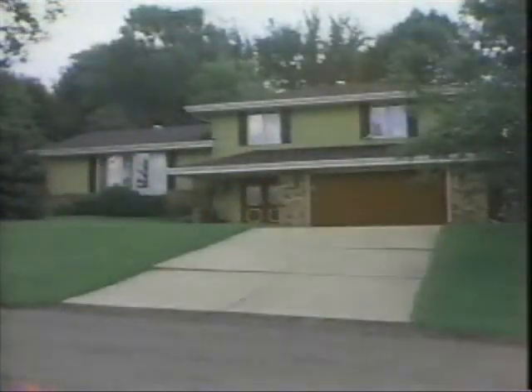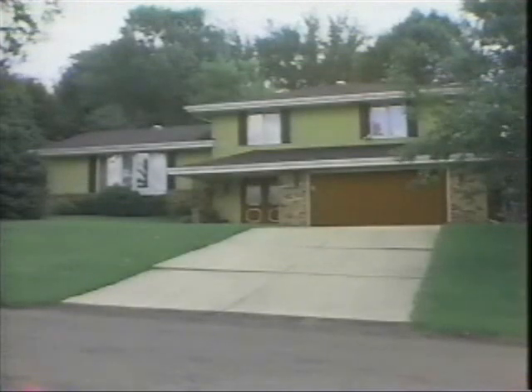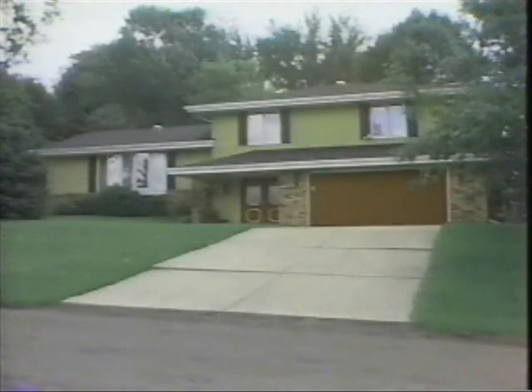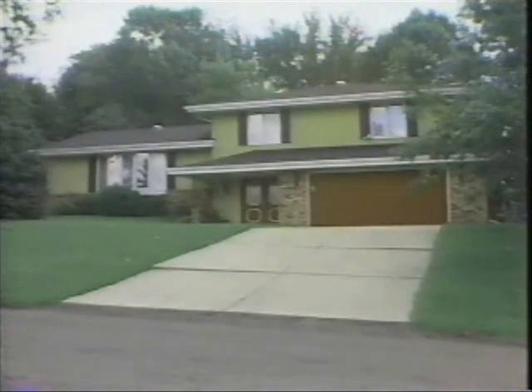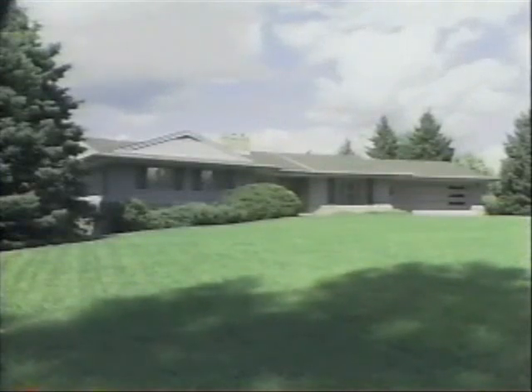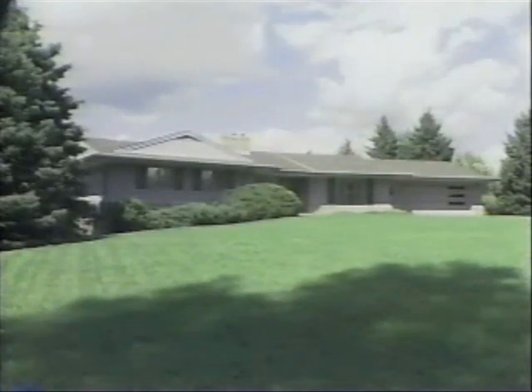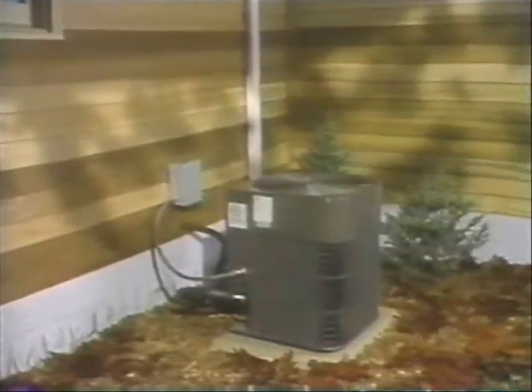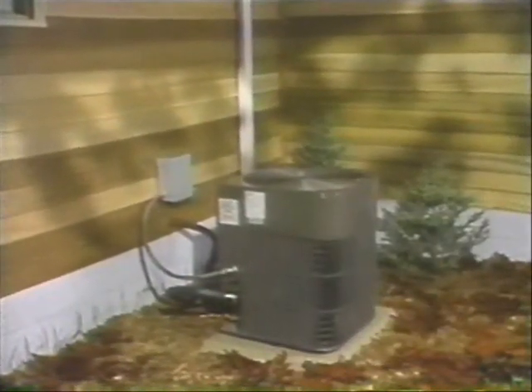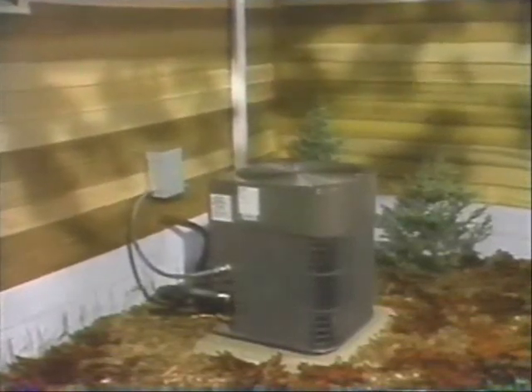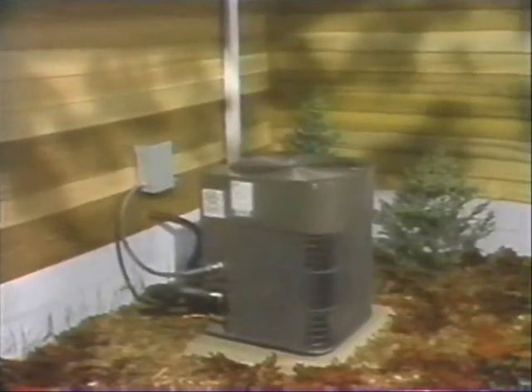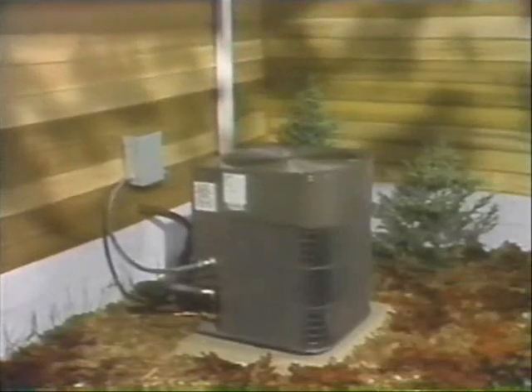Okay, now that you're familiar with the rating system, let's take a look at the switching requirements for air conditioners and the relays they use. Residential systems require compressor switching and fan switching. The compressor, of course, pulls the biggest load. In systems with air-cooled condensers, the condenser fan is wired in parallel with the compressor, and that adds to the load.